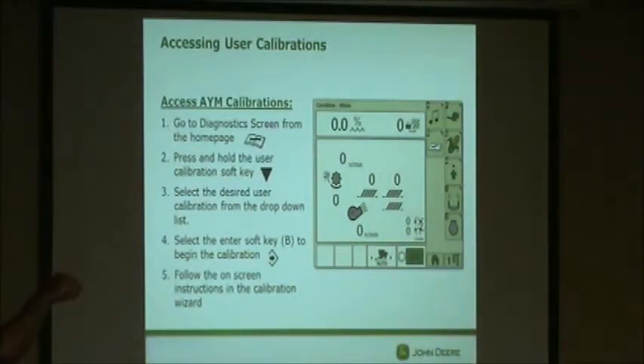The way that you get into them, you're going to go to your calibration button, the wrench in the book. You're going to get into that, and then over on this side, you're going to have another button that's going to go to your calibrations. Once you select that button, you're going to see a drop-down box come up, and you're going to highlight the moisture sensor temperature. Then once you select that, of course, enter, enter.